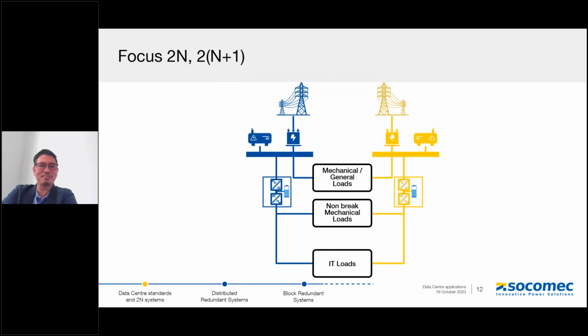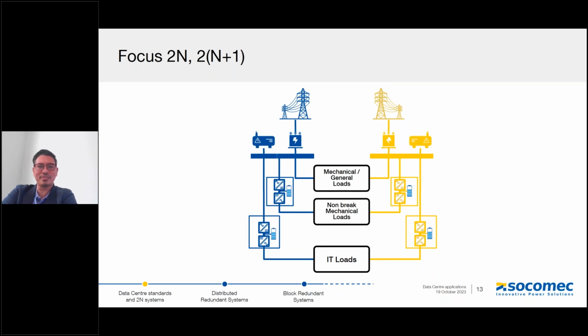As you can see here, you can have your IT loads, and in some cases with the same UPS we also supply some of the non-break mechanical loads like controllers, FCUs or chiller pump motors. But in most designs we separate those, which is what we have seen as a best practice. In data center implementations, the non-break mechanical loads are supplied by a separate UPS. This is typically in the range of 200 to 250 kilowatts. So we have a separate UPS system for the IT loads as well.